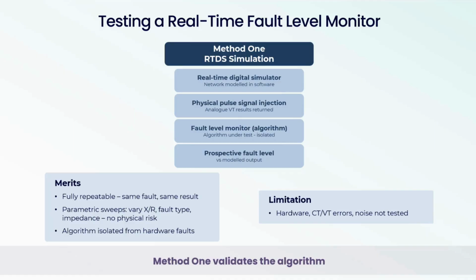We thought we could tackle this using two complementary methods. Method one would attempt to validate the algorithm in a variety of scenarios, and for method two, we'd take a complete unit to a site where we could do full system tests, actually put real faults onto a real network at real operational voltages to demonstrate that we could predict what the fault level currents would actually be. Method one could be performed on a real-time digital simulator.